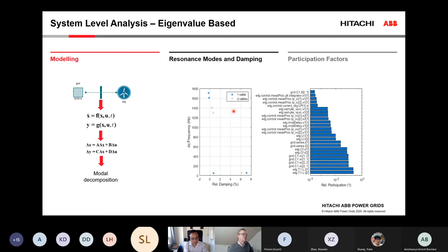Another thing you can extract from this: when you calculate the eigenvalues of this A matrix, you also get eigenvectors. Eigenvectors can be used to calculate something called participation factors. Those participation factors can be used to do root cause analysis and figure out which parts of the original model, which control loop, which grid element is mainly related to an instability that you can see.